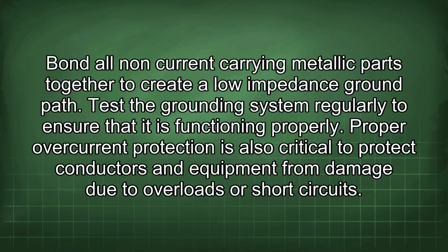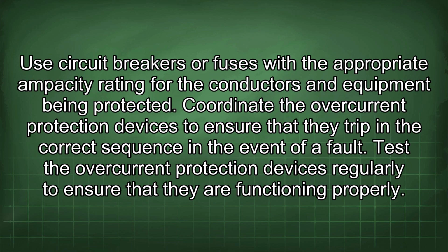Proper overcurrent protection is also critical to protect conductors and equipment from damage due to overloads or short circuits. Use circuit breakers or fuses with the appropriate ampacity rating for the conductors and equipment being protected. Coordinate the overcurrent protection devices to ensure that they trip in the correct sequence in the event of a fault. Test the overcurrent protection devices regularly to ensure that they are functioning properly.